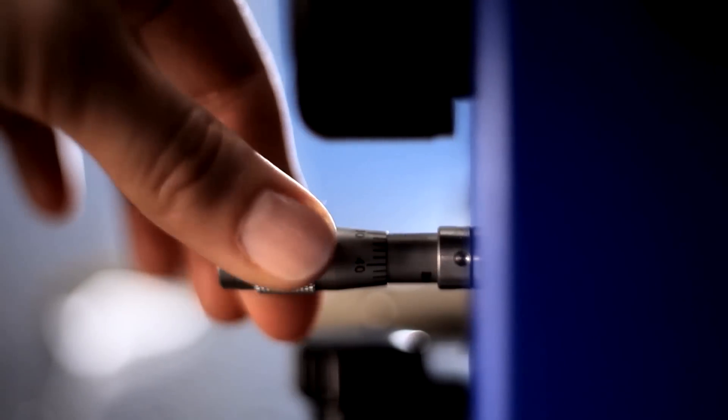To optimize the signal, turn the focus screw. Next, let's talk about how to change the optic set.